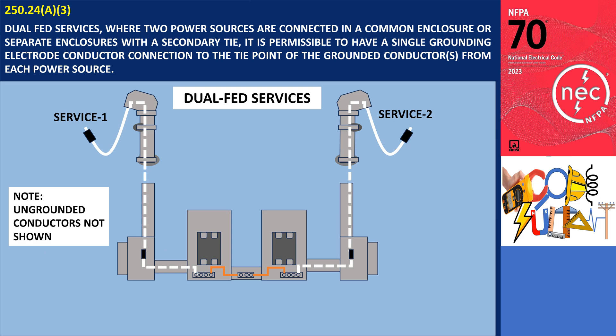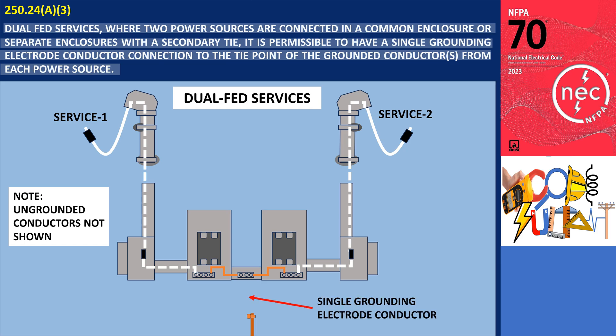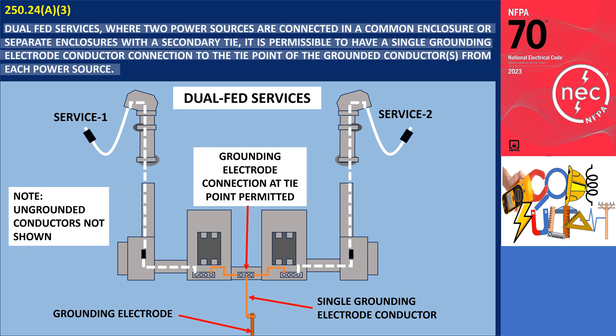According to Section 250.24(a)(3), in the case of dual-fed services — where two power sources are connected in a common enclosure or separate enclosures with a secondary tie — it is permissible to have a single grounding electrode conductor connection to the tie point of the grounded conductor from each power source. In the depicted illustration of a dual-fed system with secondary tie points, a single grounding electrode conductor is connected to the tie point of the grounded conductor for each power source.